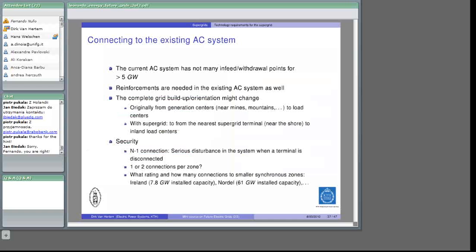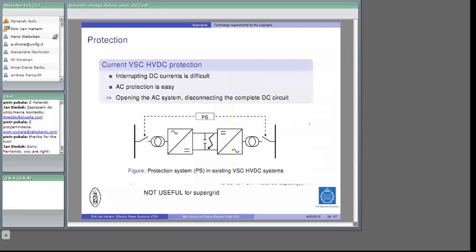Protection is often seen as one of the most difficult or most challenging tasks for the supergrid. Currently, if you think about the VSC HVDC system, the protection system works as follows. If there is a fault on the DC system, they don't interrupt the DC current, but they open the protection systems on the AC system at both sides of the terminals, and thus also eliminate the fault current. So this is the easy way.